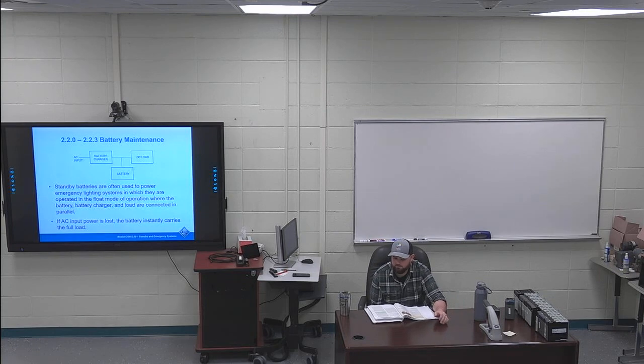Luckily for us, it's not, please help it not get above 122 degrees Fahrenheit, and we are definitely not at 3,300 feet above sea level. But those are the two numbers. I have the last sentence highlighted too. The battery charger manufacturer can provide these derating factors. If you stay in this area, you're probably not going to have to worry about those. But have those two in your mind: 3,300 feet above sea level, and if you're over 122 degrees Fahrenheit.